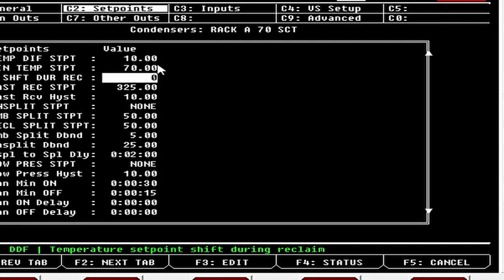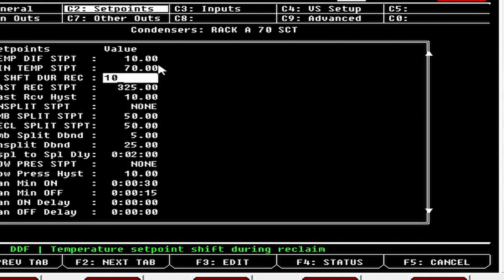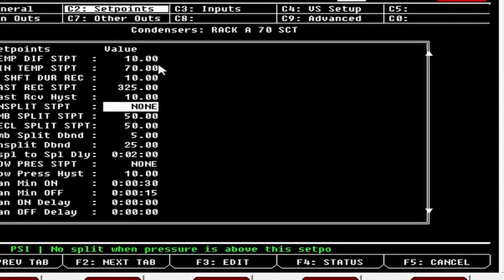Temp Shift During Reclaim: a lot of customers use this to force up the head pressure during reclaim. You could put 10 here, so when reclaim is active and your set point is 70, it shifts it up 10 degrees to 80. Not the best approach up here because gas heat is cheap — it's cheaper to run gas heat than to run the rack up — so I don't like to use it.